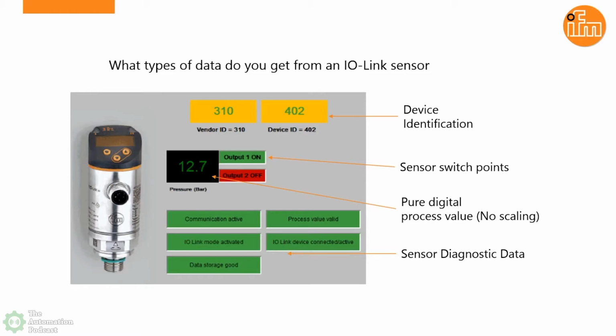In this case, on this HMI, I'm showing it's 12.7 bars. That's actually what you're going to see in the PLC. And then you have a host of diagnostic information and flags that you're able to pull, and that's all part of the standard IO table when you're looking at IOLink. The only major difference when you're employing IOLink is that you just have a larger data array to work with for each device, and you can choose to use as much of that or ignore as much of that as you want.